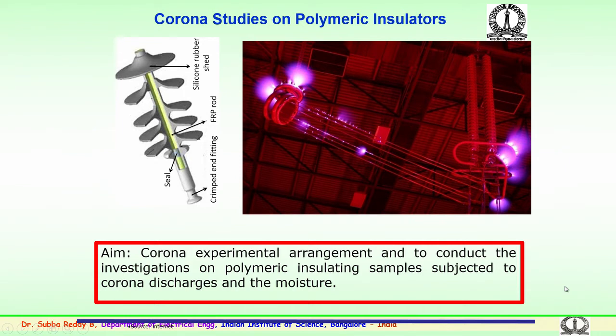Various types of samples are to be subjected to corona discharges during normal conditions, that is the dry conditions, and also to see the performance during moisture. Moisture means light rain, drizzle or fog. This aggravates the corona activity, and the combination of corona with moisture would further degrade the surface of the polymer. This has to be studied in detail, as very little information is available in the literature, since these insulators are of recent origin. So, studies have to be carried out on this aspect.